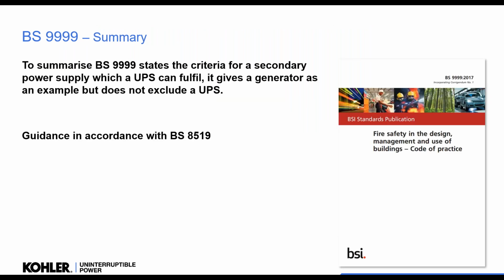So for 9999, it states the criteria for a second power supply, which a UPS can fulfill. It gives generators as an example, but does not exclude a UPS, and it actually says to follow guidance in accordance with 8519, which talks about how we're going to install a UPS correctly.